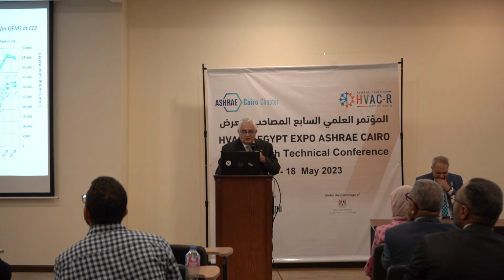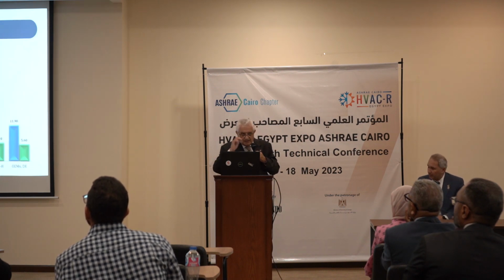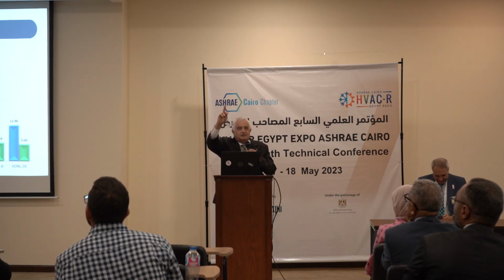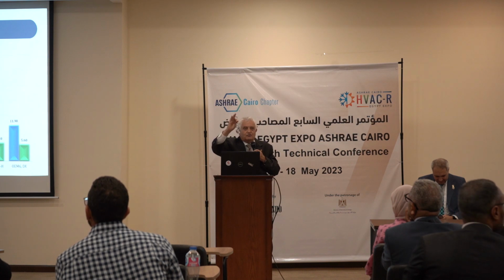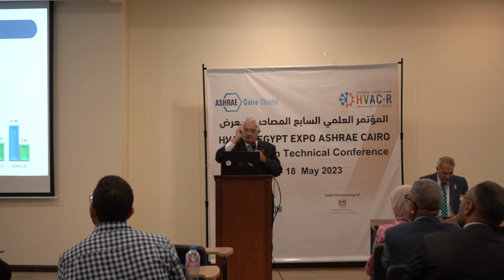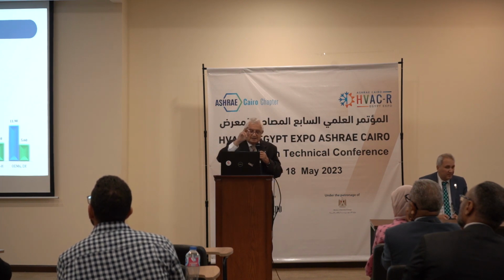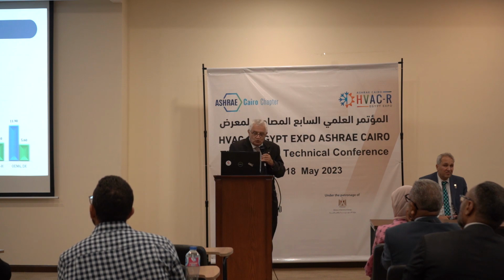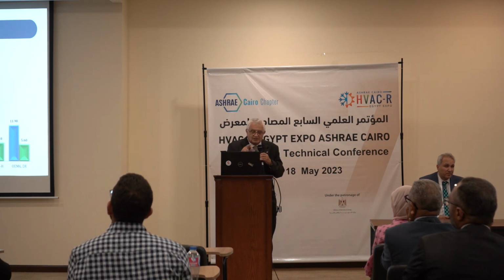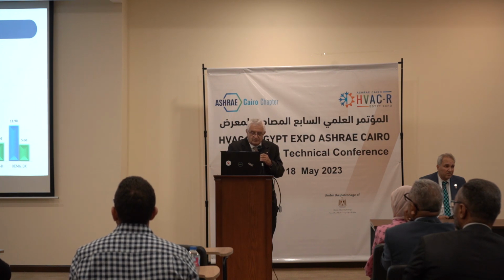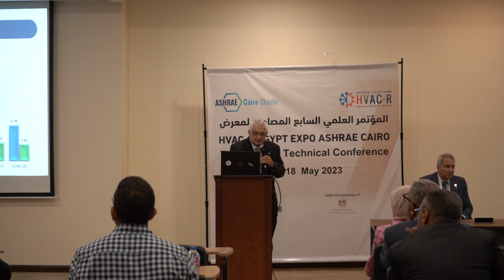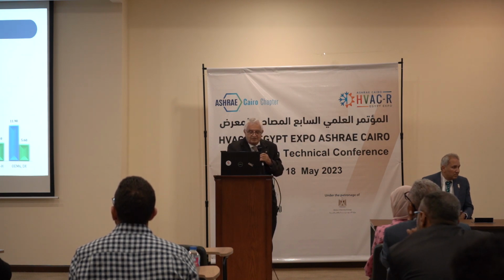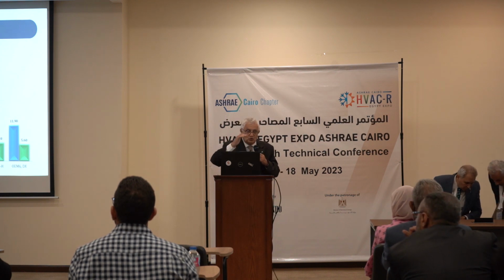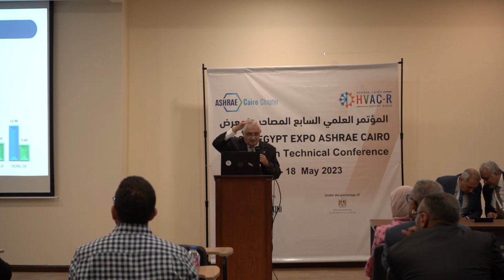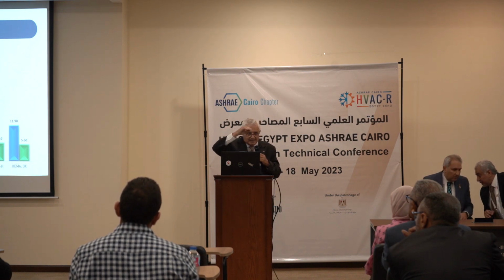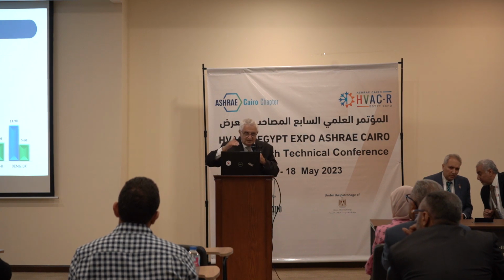Now, to move to the end results, if we compare the EER at the climatic zone of the 4 manufacturers that worked with us, you'll find that you have a blue line and a green line. So OEM2, the EER, the blue line, was higher than that of the DX machine just next to it. One is 18.17, the other one is 15.63, so it's better. I'm talking about the blue because the blue is the high. There is a high EER at the zenith of the day, and the lower EER where the humidity is higher at night.